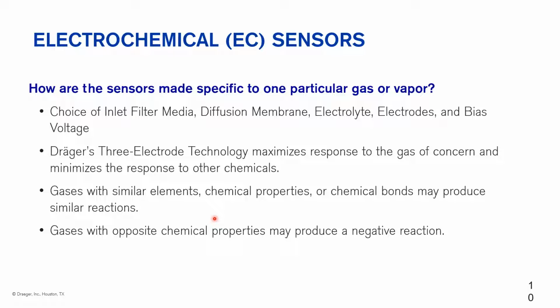Hydrogen on a CO sensor: a standard CO sensor is going to respond to hydrogen. Generally it doesn't matter who makes the CO sensor. Yes, there are hydrogen compensated or hydrogen resistant sensors out there, but standard sensors, they're going to respond to hydrogen. But for the negative reactions, one that was always interesting was NO2 and SO2 sensors. NO2 and SO2 have a negative response on the other sensor. So if you had a situation where you had both NO2 and SO2 present, the reactions could basically cancel each other out, and you end up with a 0 reading on your instrument when you could have hazardous levels of both gases present.